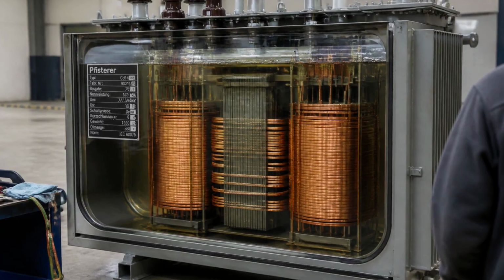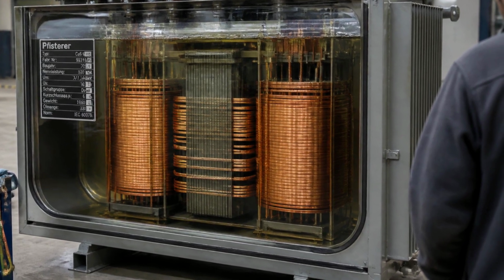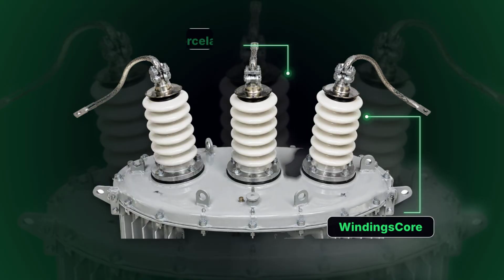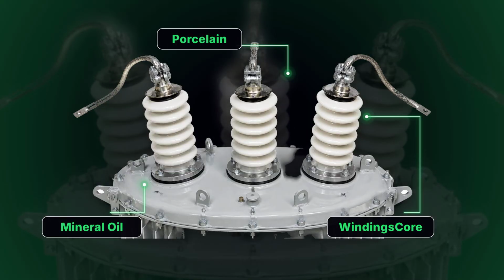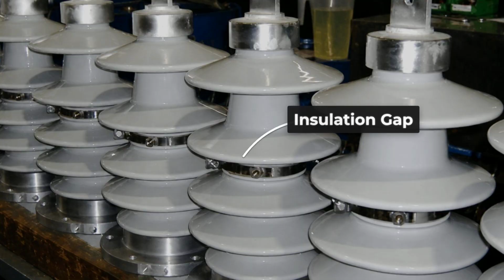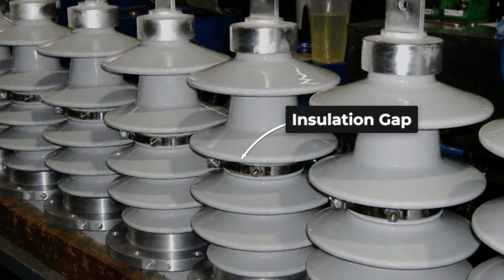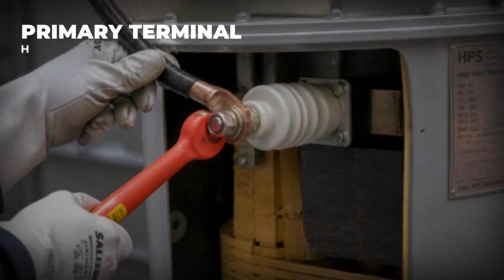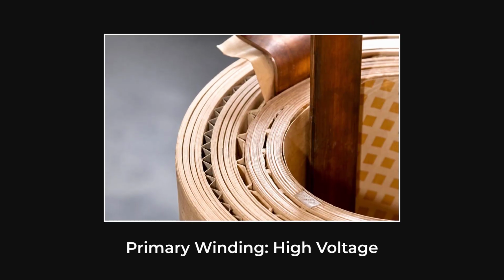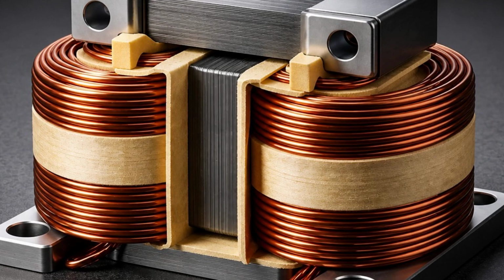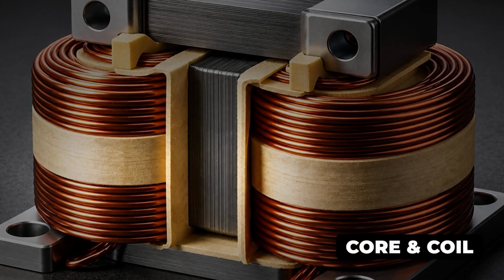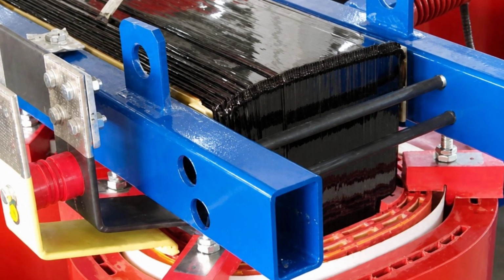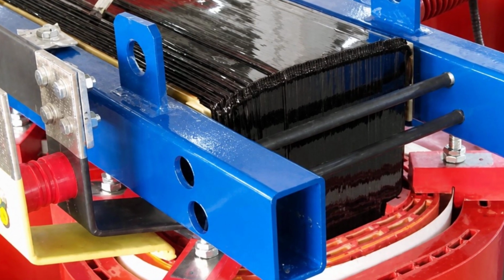To step this power down, the electricity must pass through a carefully arranged sequence of internal components. Porcelain bushings protruding from the top act as insulated gateways, carrying the high-voltage utility lines through the metal tank without letting the current touch the outer steel shell. Once inside, the incoming line connects to the primary winding, a tightly wrapped coil of insulated copper or aluminum wire. This coil wraps around a heavy, laminated steel core made of thin, insulated sheets designed to carry magnetic flux with minimal energy loss.